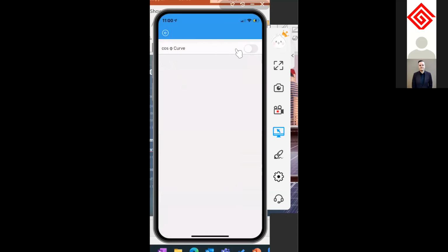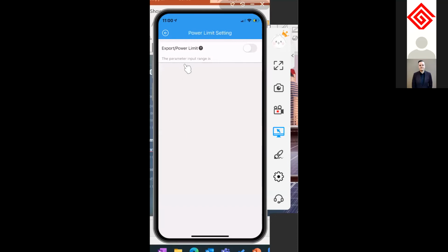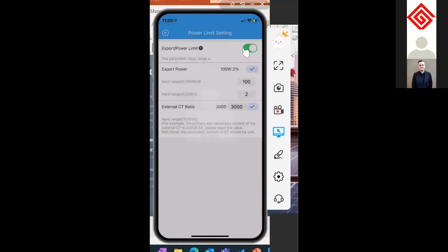Yes, it's loading a bit. So you can activate this. If going back, here is the power limit settings, and because we do have installed a smart meter, we will activate this, and then activating it here, you can input the power range here, and also the percentage. And then here you need to input the CT ratio, and the CT ratio is, it says here in the example here, the primary and secondary current of the external CT is 300 amps divided by 5, which gives you the primary.